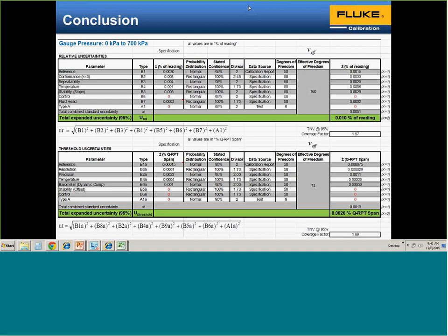And that's the question asked about the deadweight pressure gauge and resolution. You have a calibration of your masses, you have your mass resolution, and then you have using trim mass. That really determines how well you can calculate or measure your pressure. If you're using some software to figure out your pressure, like Pascal or your own spreadsheet, it's typically based on what Tim said: the sensitivity of the lowest mass you can use, and the resolution of your mass.